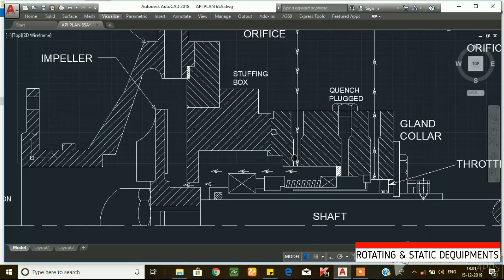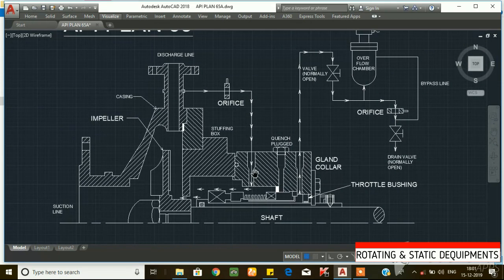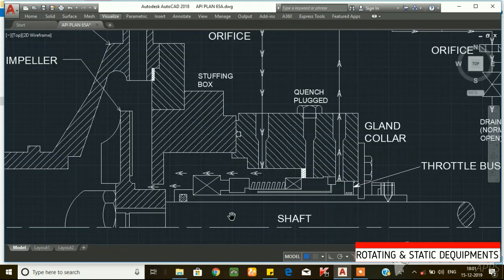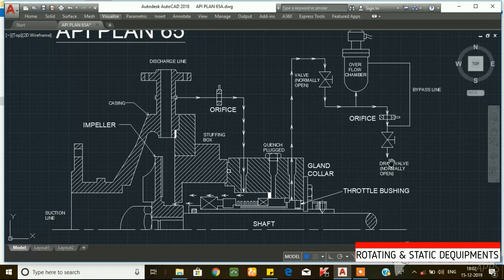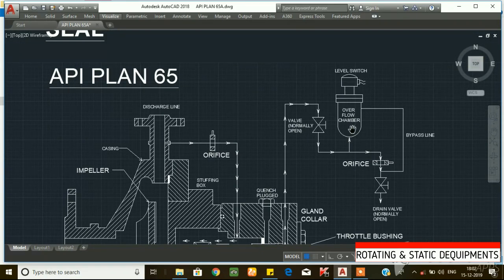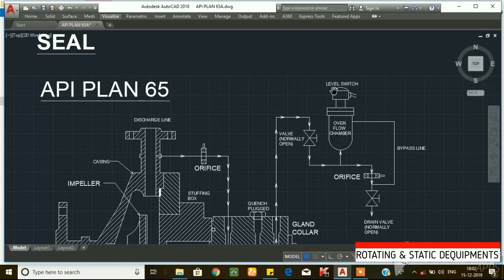If the mechanical seal works normally, no issue. In case the mechanical seal fails, there will be leakage from the inside port — this is the seal face leak. This leak goes to the drain valve, because you can have a minimum leak on it. In case the leak is very excessive, it fills the overflow chamber. The level switch triggers a high-high alarm that will stop the pump.